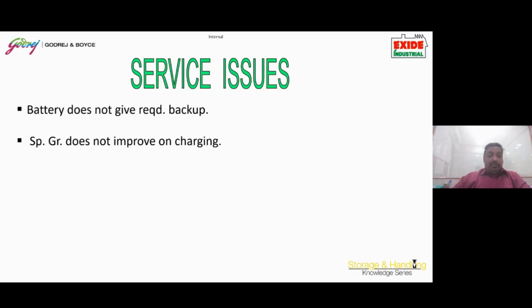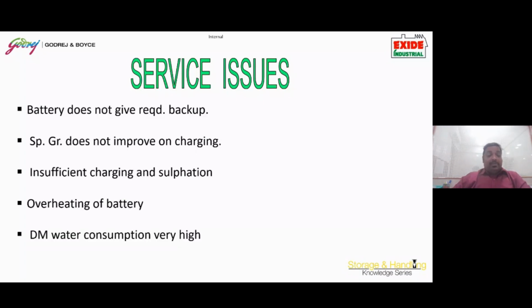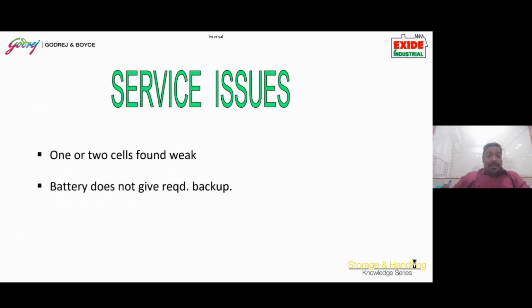Specific gravity does not improve on charging, insufficient charging and sulfation on the terminals. Sometimes overheating of battery happens. Some customers complain that twice in a month we have to do top up, meaning DM water consumption is very high, and some malfunctioning of the charger. Out of an array of 24 or 48 cells, only one or two cells are found weak, and then we investigate the root cause.